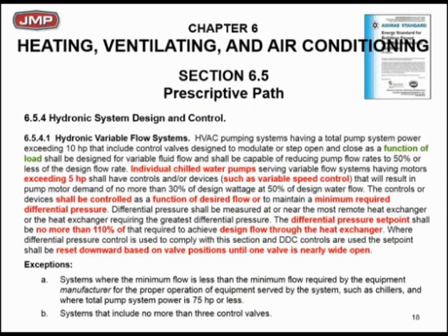So ASHRAE's driving you to lower kW as you vary that flow. So they're saying to you, let's look at half flow. Let's look at half load. Don't just look at peak. Don't just look at 100%.